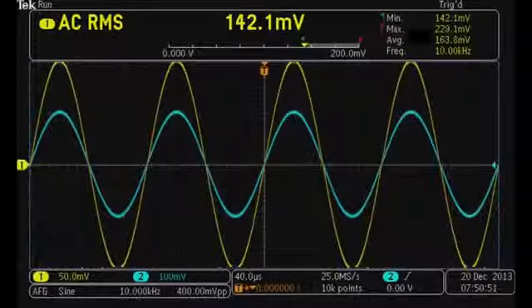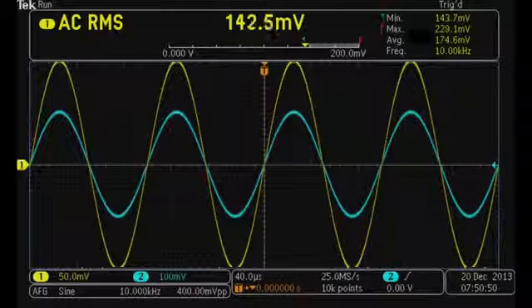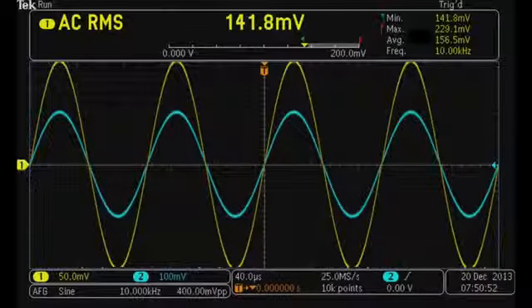The DVM doesn't rely on the oscilloscope trigger system. It free runs, so measurements are always available, even when the oscilloscope is not triggered.